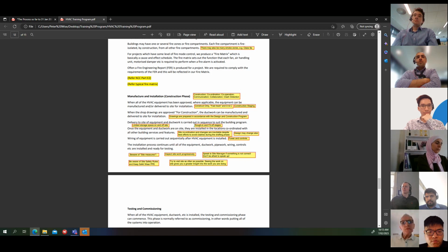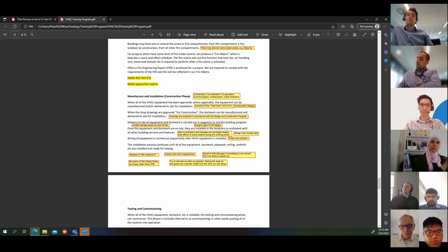Now, I've also mentioned rough-in and fit-off stages. The rough-in stage is work basically that's above ceilings. So getting in ductwork above ceilings, pipe work, equipment, wiring - everything associated with mechanical services. Being 'rough-in' is probably not a good word because it's not that rough - it's got to be put in properly and accurately. But it gets it in above the ceilings. Then the builder can come along and get the ceilings installed, which he's always keen to do, and the ceiling contractors are chomping at the bit, wanting to get started.